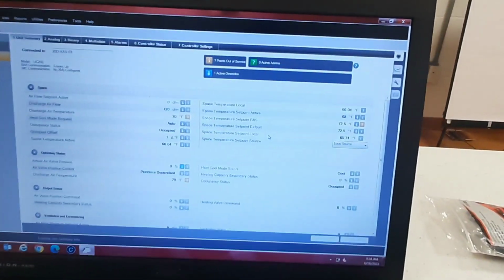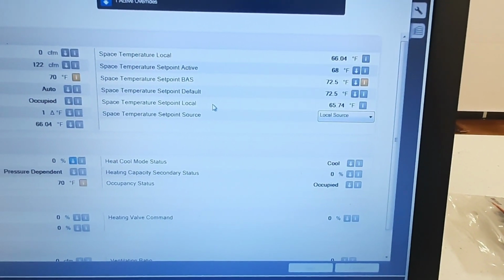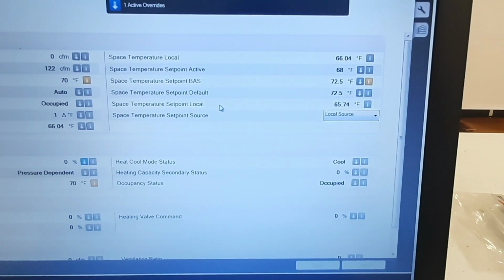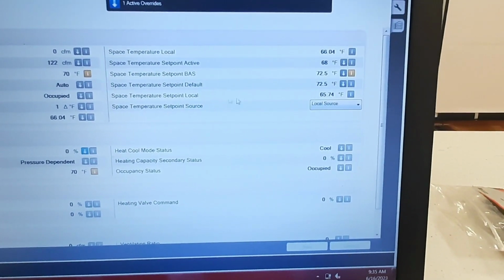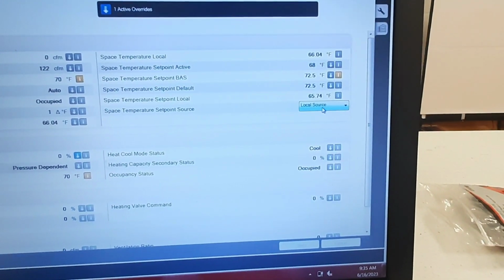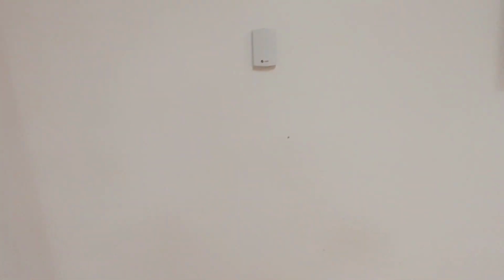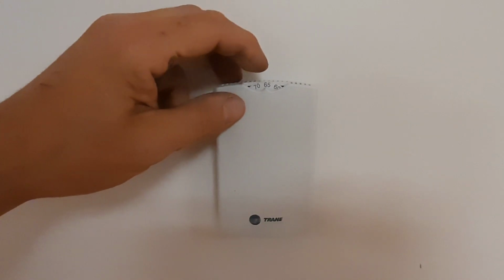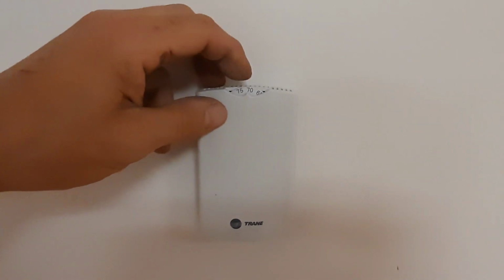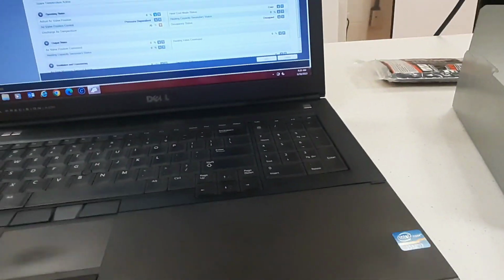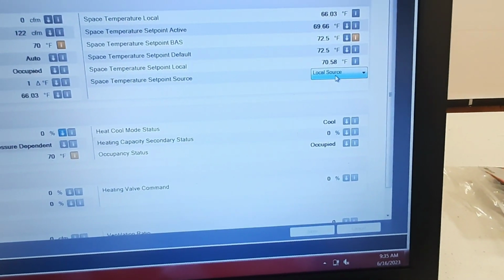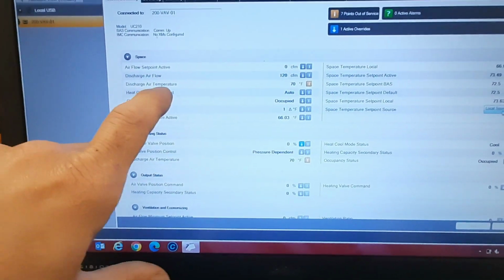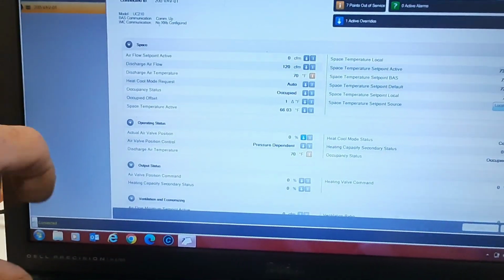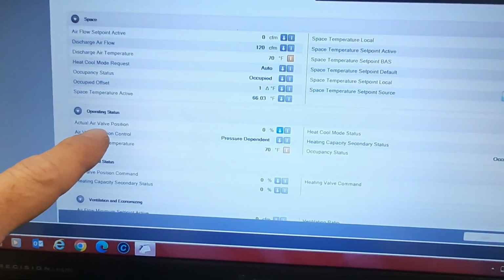So space temperature right now showing 66. Set point local is going to be the set point of that sensor. It's at 65. It is local source, so that means we're using the local set point to set our temperature. So you can see we're at 65 right now. Turn it up, and we'll see my set point changed. Now I am showing 120 CFM. Not sure why I'm reading some, because my actual air valve position is 0.